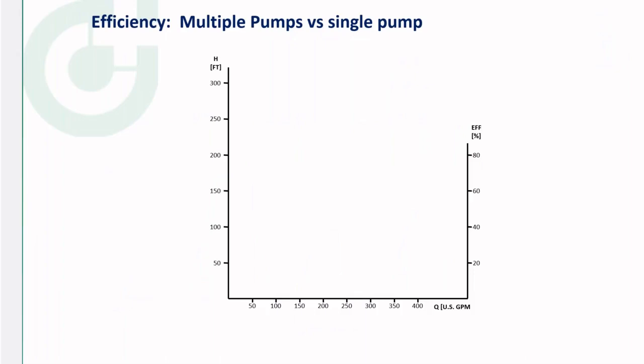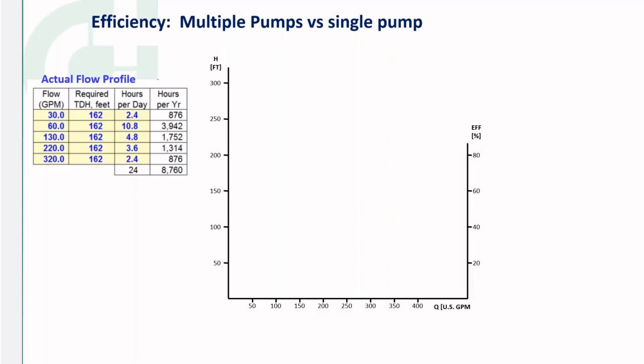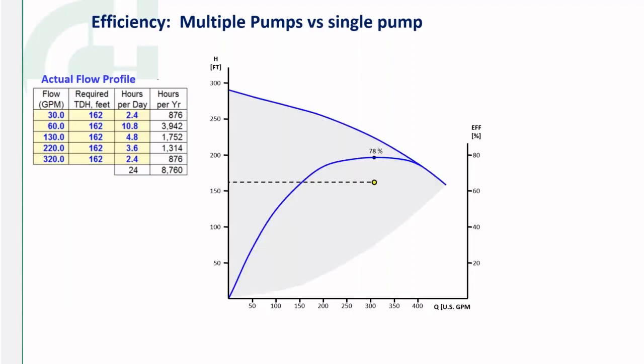Okay, so now that we have a basic understanding of flow profile, we can put this to use with a quick example. We've got an arbitrary flow profile. Max design flow is 320 GPM, and we spend about 2.4 hours a day at that flow. Of particular note is the flow rate of 60 GPM, where we spend 10.8 hours a day. Our max design point, the dotted line, is our constant pressure control curve, so as the flow drops, pressure stays the same. Let's say we select a single pump for this duty point. The top blue line is the pump curve, and the bottom blue line is the efficiency curve. At that 320 gallons per minute, we're at about 78% efficiency, which is pretty darn good, right?